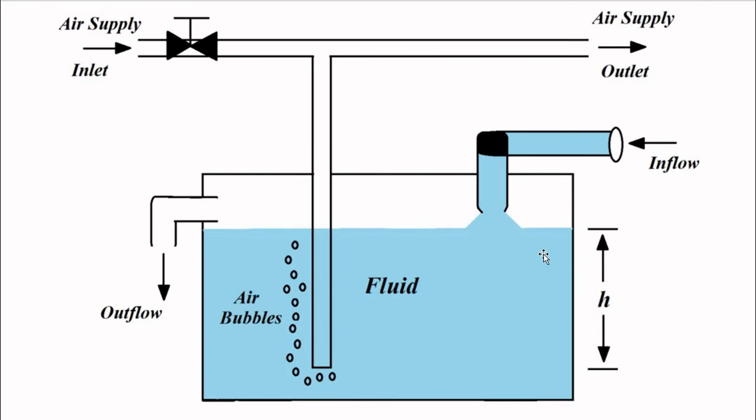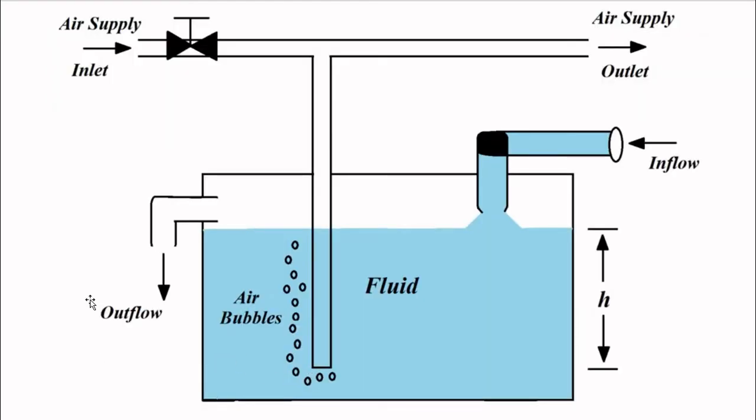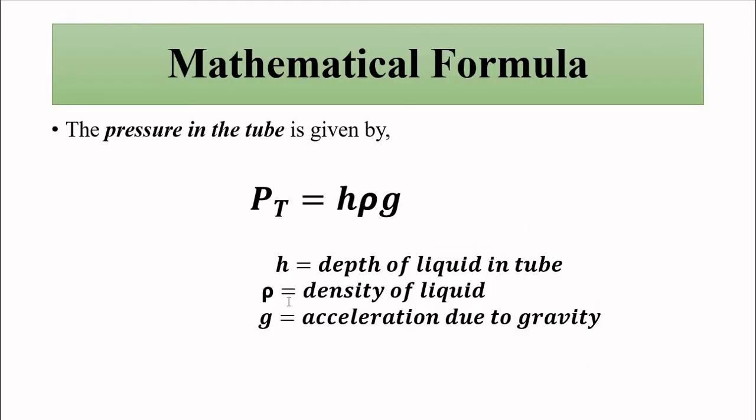Level sensors are there. Whenever level crosses upwards, an alarm is triggered and outflow and inflow are regulated so that the level in the container is fixed. So h is fixed, then acceleration due to gravity g is fixed. The only thing that controls the pressure in this tube is the density rho of the liquid.